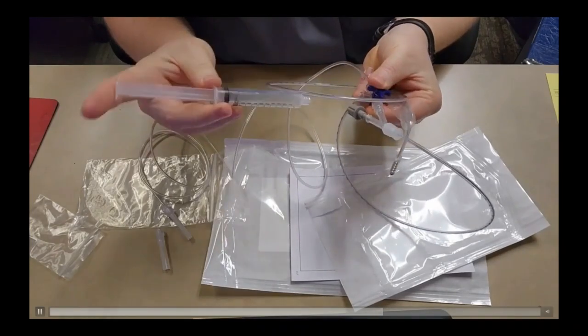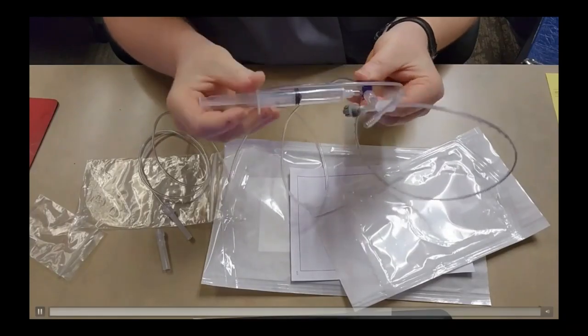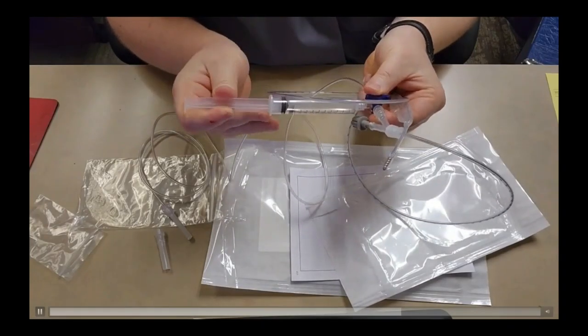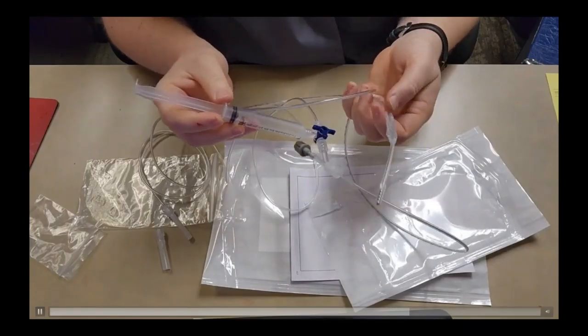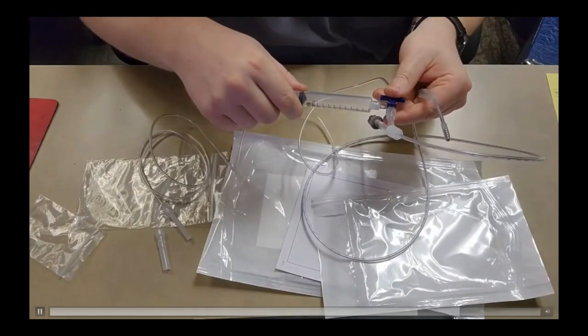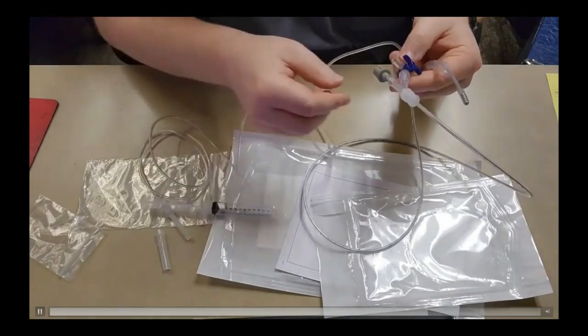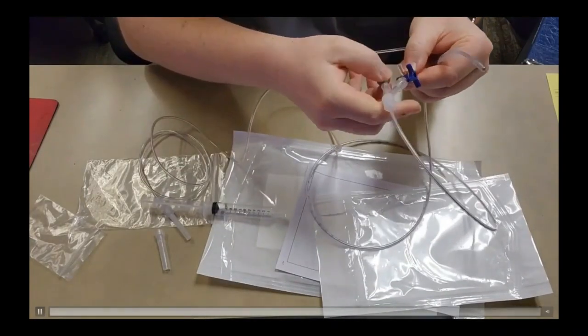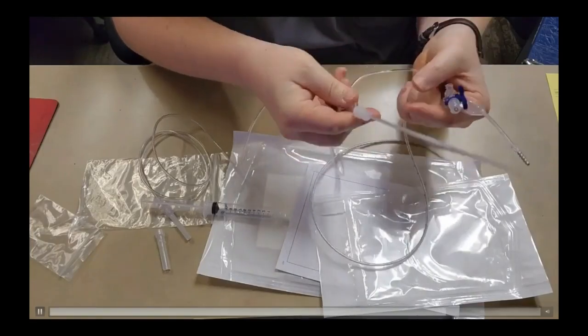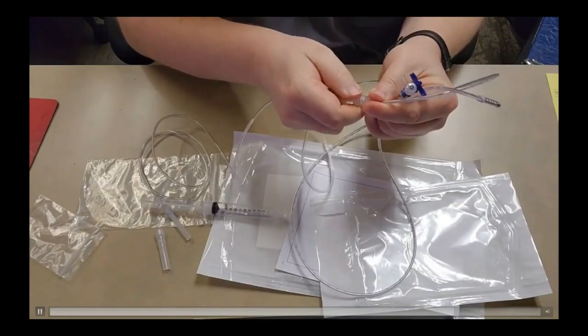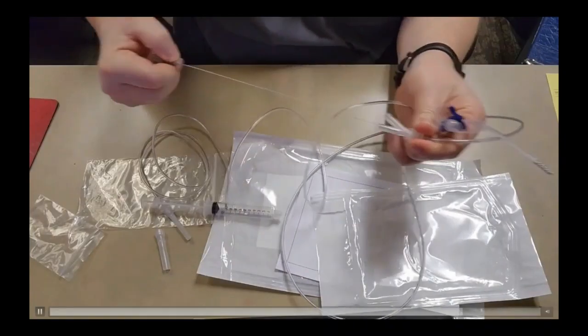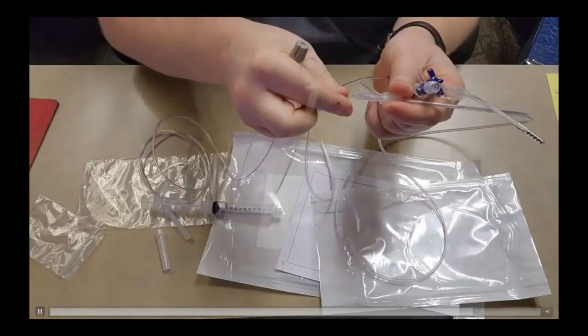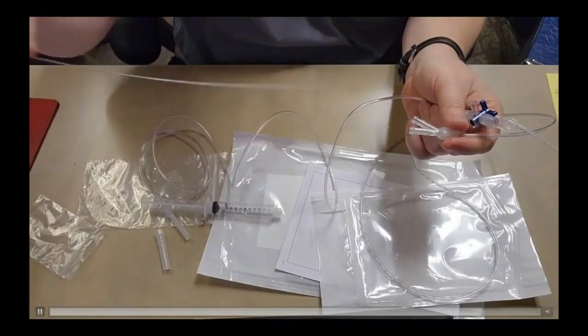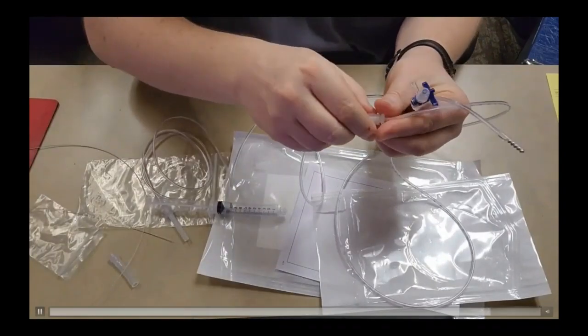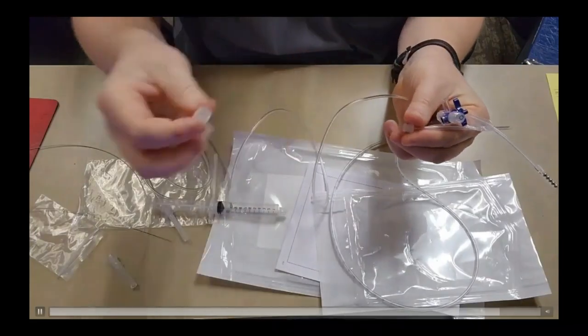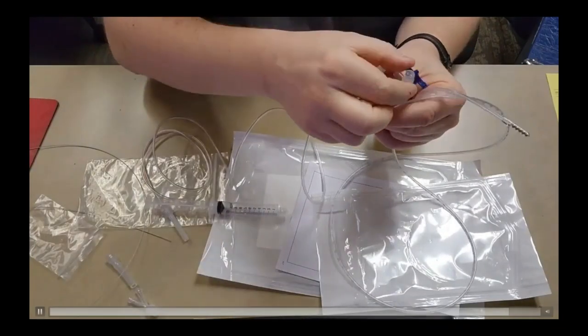In order to verify proper placement, an X-ray must be taken. Now, after the catheter has been verified by X-ray, you will need to remove the guide wire. Removing this guide wire will allow for the catheter to remain in place if the need for an MRI occurs. We have also found that the plastic at the Y has a tendency to crack and can affect the readings. So we have found it to be best to remove all of it.